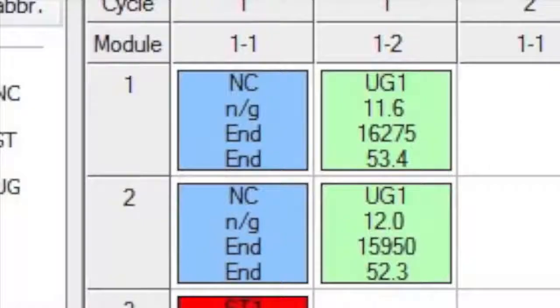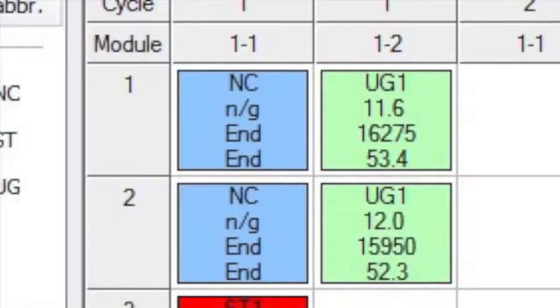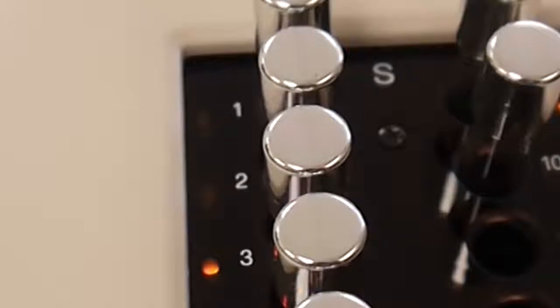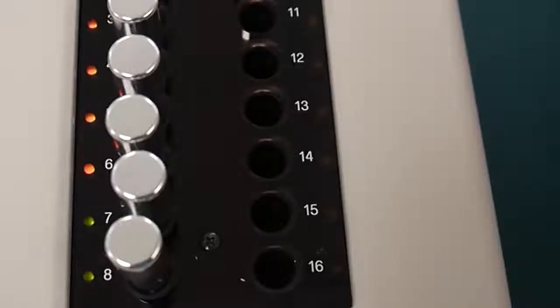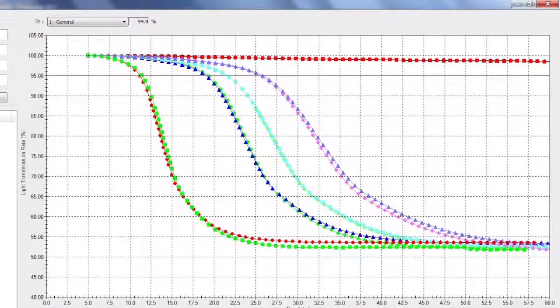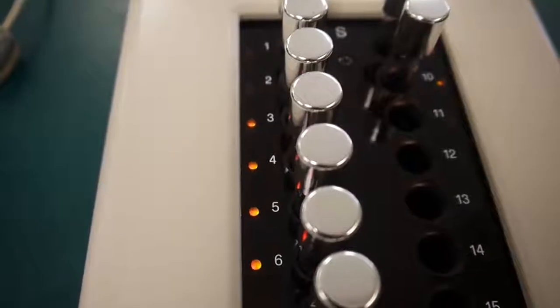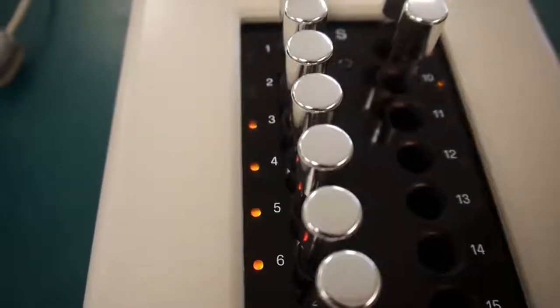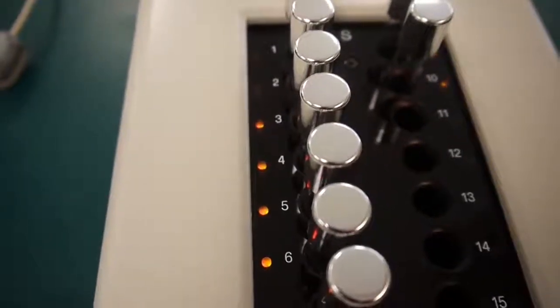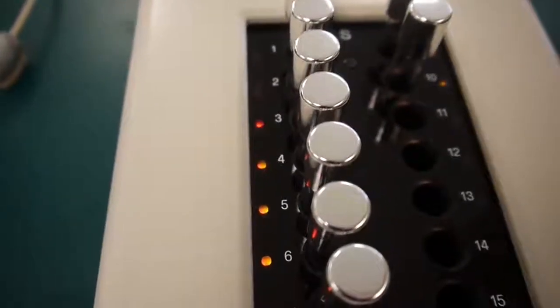When the testing cycle ends, we note that the negative control did not gel. Cycles which have ended without gelation show a blank LED light next to the number of the sample. As our samples continue to gel, we notice the orange lights. As our samples reach the end of the timed cycle, we notice that samples which have gelled during the timed cycle beep and show red next to the sample number.